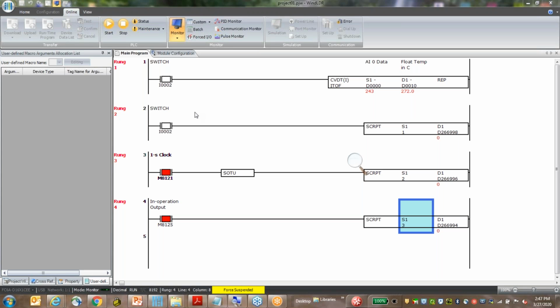Does the destination register become a float since you use 10.0 in the equation? If you would use 10, would that make it an integer? Well, I want it to be a float because I don't want to mix and match my data registers. But yes, it would be an integer unless I change it to a float. But since I'm adding a 10.0 to it, I'm changing it to a float. And the reason I did that is because I need it to be a float for the next rung of code.